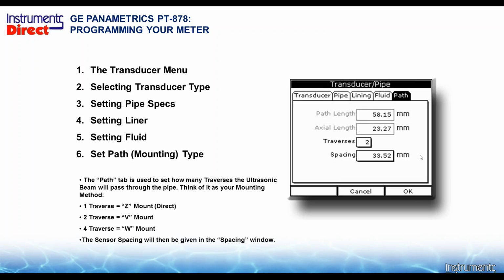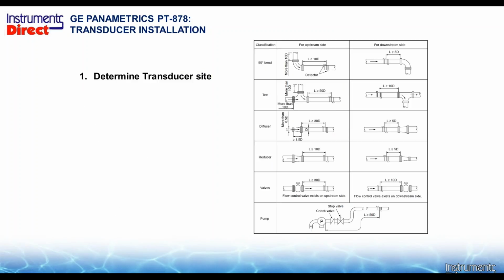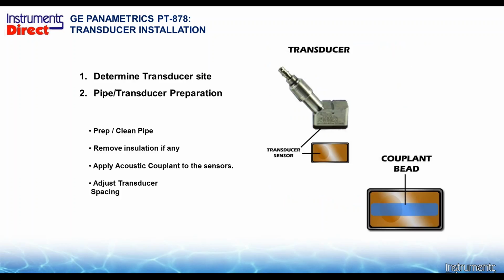And then the meter will tell you what the spacing is. Again, this is millimeters, but if you program the meter in English, it'd be in inches there. This is the differential spacing from transducer end to transducer end. In determining the sites, we need so much straight run of pipe. If you read the operation manual, you will find out that there is no application in the world that has enough straight run of pipe to use it on. So as I said, just stick to the generic rule of thumb, 10 and 5, when you have an elbow to elbow. If you've got some monstrous thing before, a butterfly valve, something like that, then a little bit more. So keep that in mind. That's probably your hardest obstacle.